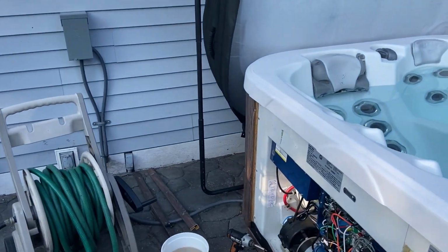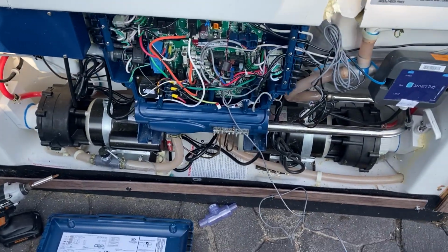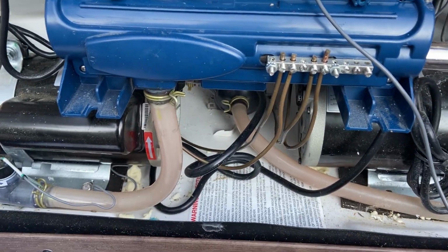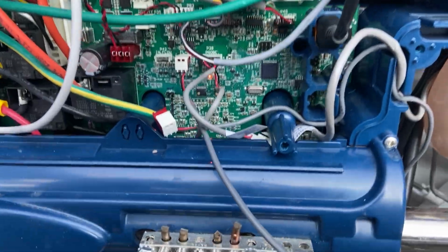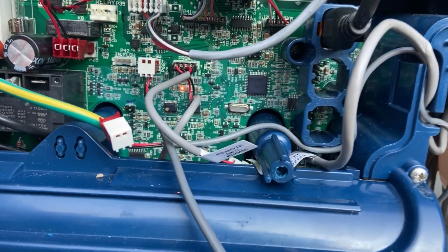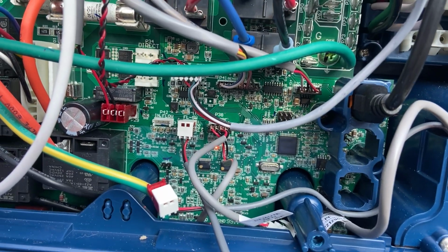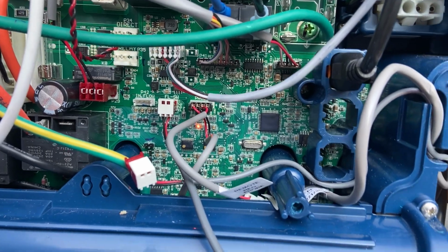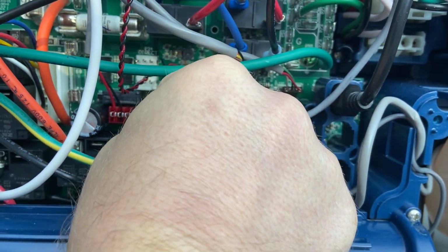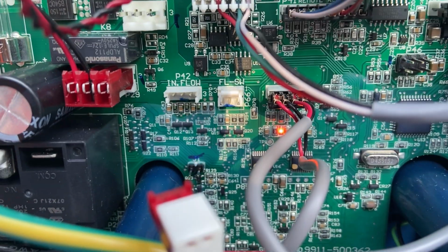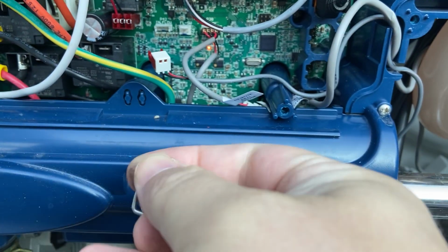So let's come around here again. And we're gonna do a nice little trick here. So normally I would use a flathead screwdriver or something like that. In this case, I don't have one with me, but I'm just gonna show you something real quick. So if a technician or customer does not have the capacity to do what I just did, plug in a flow switch, test it by closing it, I'm gonna jump across these pins. So we see 3 pins there.